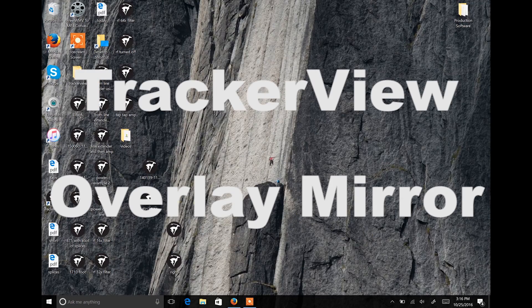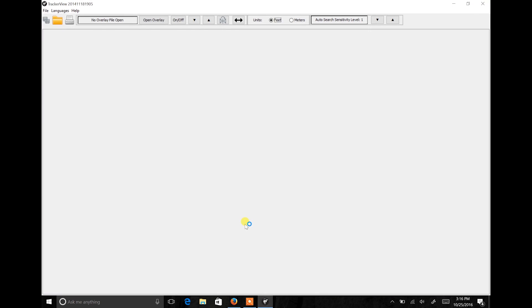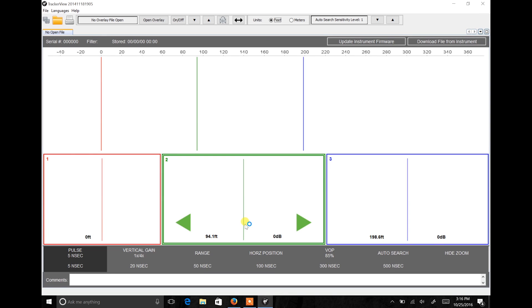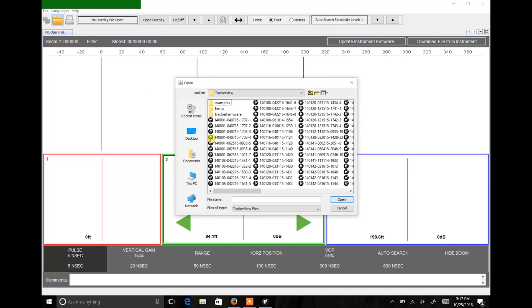It is always best to test a cable from both ends. It can help reduce error in VOP and uncover hidden faults. A reduction in the TDR pulse energy caused by attenuation or cable loss can make a small fault difficult to see if the fault is a long distance away.